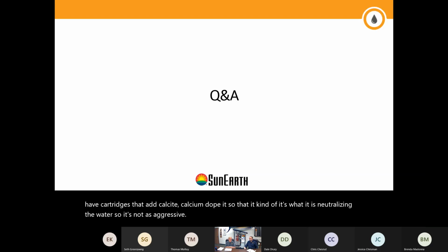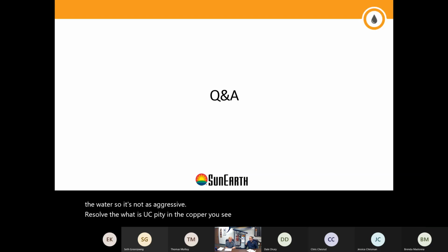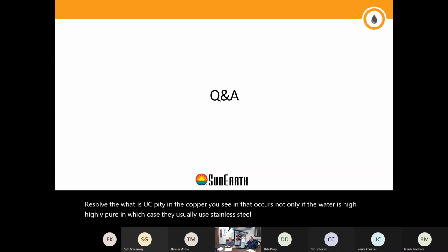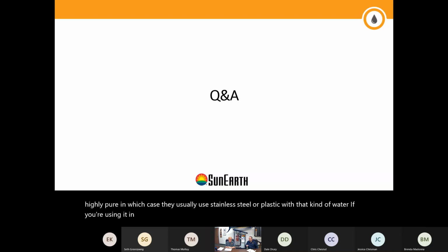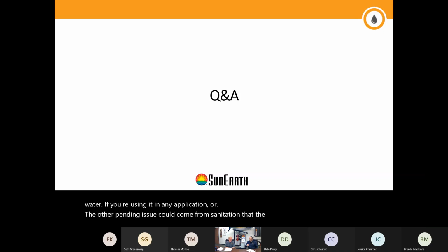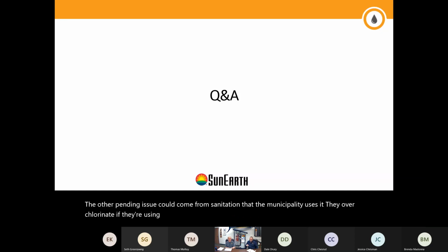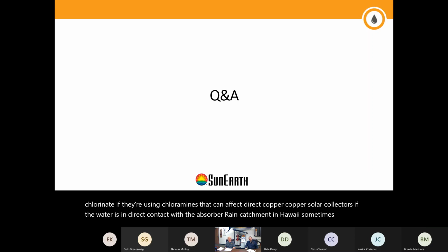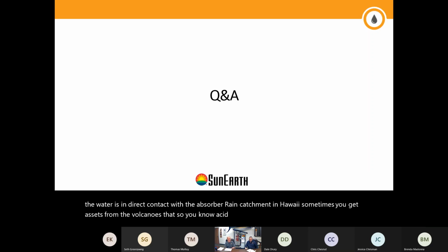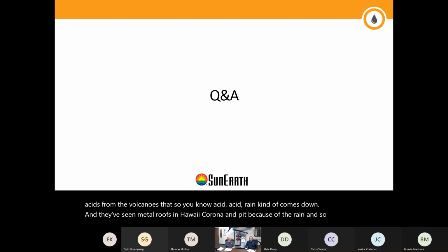The result is you see pitting in the copper, and that occurs not only if the water is highly pure, in which case they usually use stainless steel or plastic for that kind of water in any application. The other pitting issue could come from the sanitation that the municipality uses. If they over-chlorinate, or if they're using chloramines, that can affect direct copper solar collectors if the water is in direct contact with the absorber. With rain catchment in Hawaii, sometimes you get acids from the volcanoes. Acid rain comes down, and they've seen metal roofs in Hawaii corrode and pit because of the rain. So if they're doing catchment, they have to treat it.